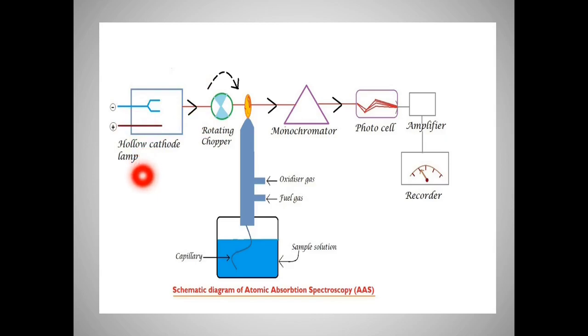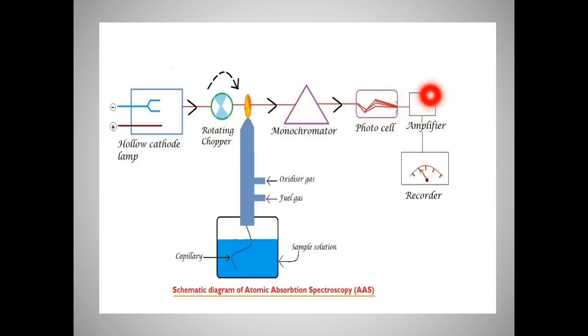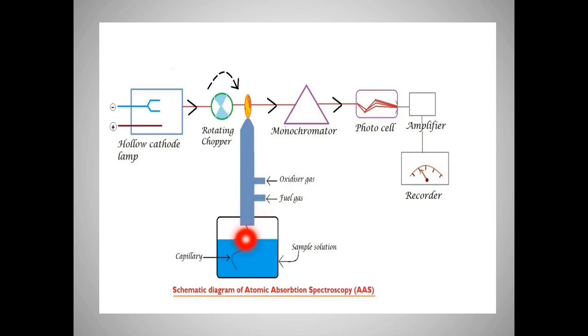The source used in AAS is called the hollow cathode lamp. I will explain how it produces the characteristic radiation that can be absorbed by the sample. The remaining components include a rotating chopper, monochromator, photocell, amplifier, recorder, and a burner to atomize the sample. When the sample is atomized it is in the gaseous state and has the ability to absorb light.